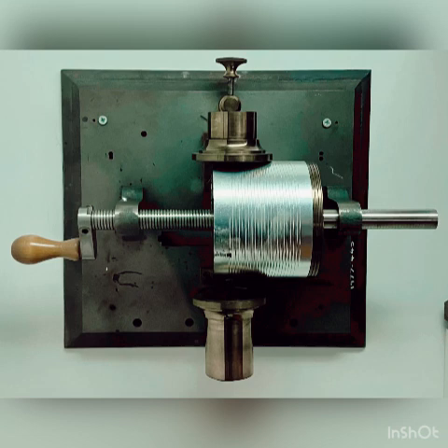Annual calibration of an audiometer. Frequency to be within plus or minus 3% of the indicated frequency. Intensity. Absolute intensity should be according to the table of reference equivalent threshold sound pressure levels. All figures refer to TDH39 headphones calibrated to BS2497. For example, 0 dBHL at 1000 Hz using TDH39 headphones, the audiometer should produce a sound pressure of 7 dB SPL in a 6cc coupler.